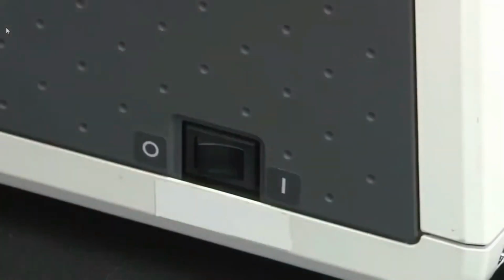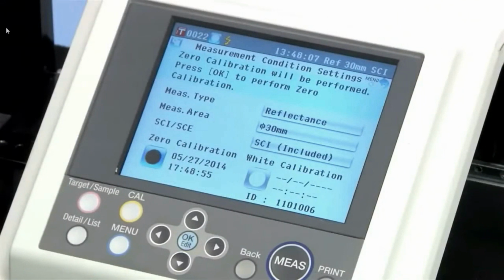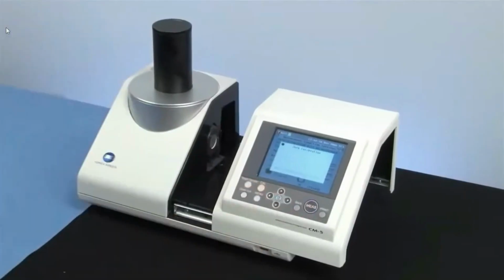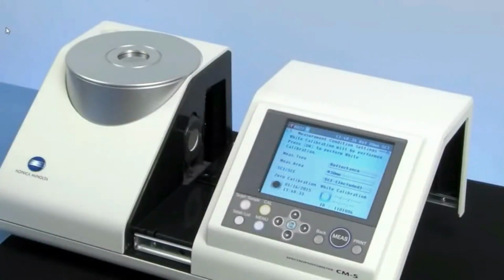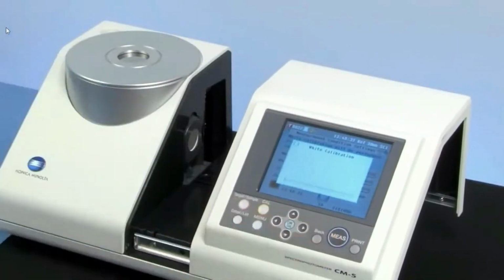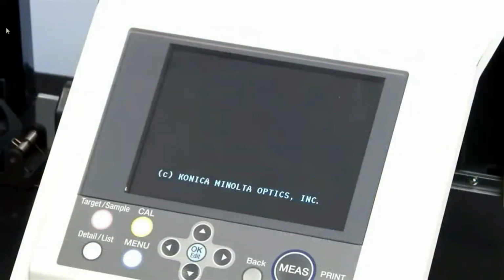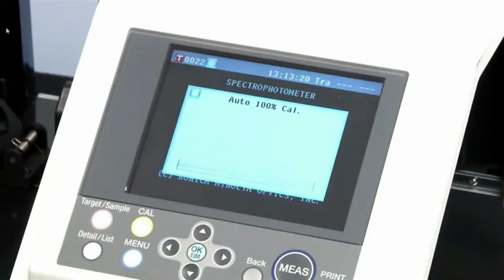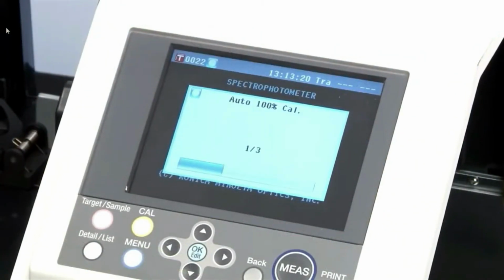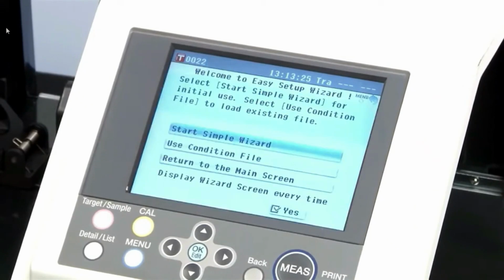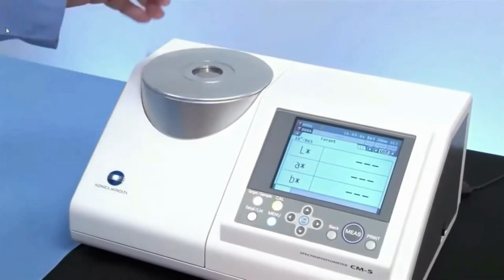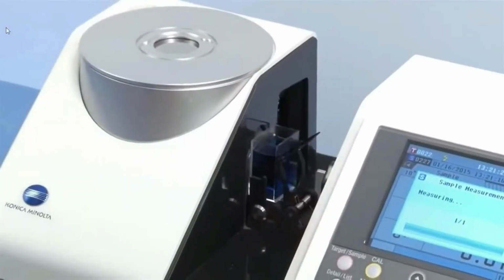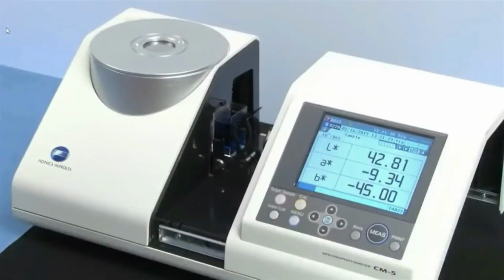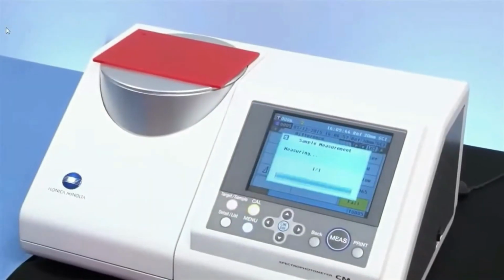To begin, just switch the instrument on, perform zero calibration, and then white calibration before each color measurement session. There is also an option to perform white calibration automatically. After calibration, place your sample on the top port or in the selected transmittance sample holder and press the measurement button. What could be easier?